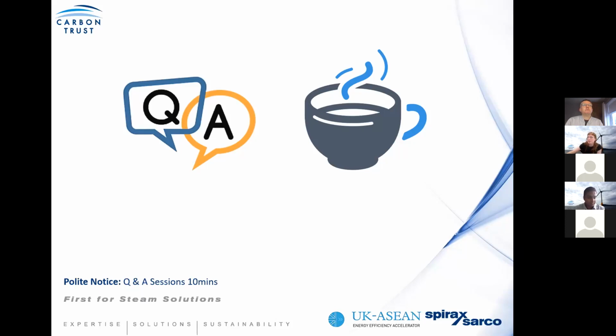Where is the best place to install a vent from a receiver? Can a long vent line be a problem? Yes. If you take any pipe that has restrictions to flow, it creates back pressure. So what we have found for certain industries is that, due to whatever reason in the production area, you have a very extended vent pipe going to, say, a roof level.